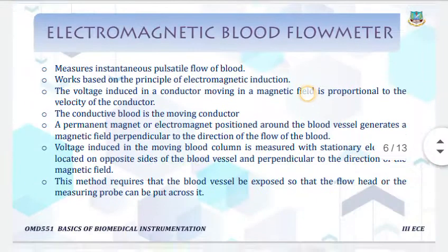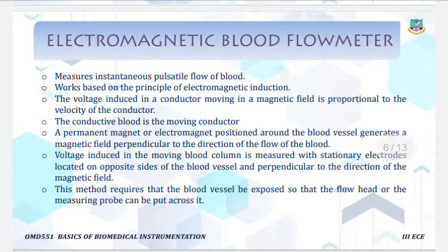This meter measures the instantaneous pulsatile flow of blood. It works based on the principle of electromagnetic induction. The voltage induced in a conductor moving in a magnetic field is proportional to the velocity of the conductor. The conductive blood is the moving conductor.